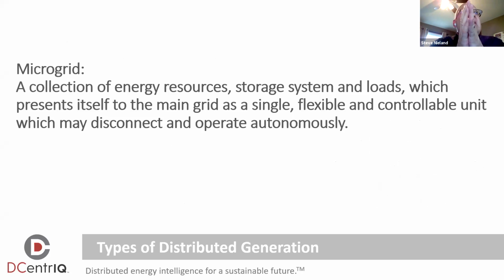A microgrid is a collection of energy resources. It can include generation like solar, a wind turbine, or a hydro system, plus a storage system to store the energy, and loads. The storage system is the important component here. It presents itself to the main grid as a single, flexible, controllable unit, so when the utility or grid sees it, there's one connection point, even if I have half a dozen generation and storage assets behind it.